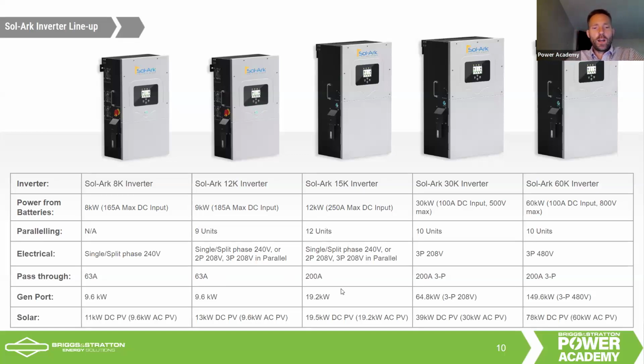And I'll also point out that one of the reasons we really like the Sol-Arks as well is how easy it is to integrate generators. So with a 15K, you've got 19 kilowatts of continuous power that can come in. That's 80 amps AC that can come in through the generator port. You can bring in more power than that through the grid port.